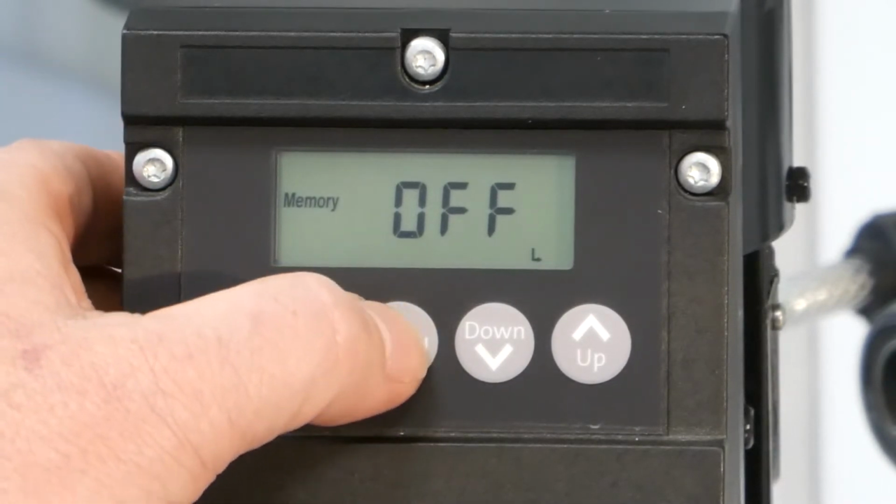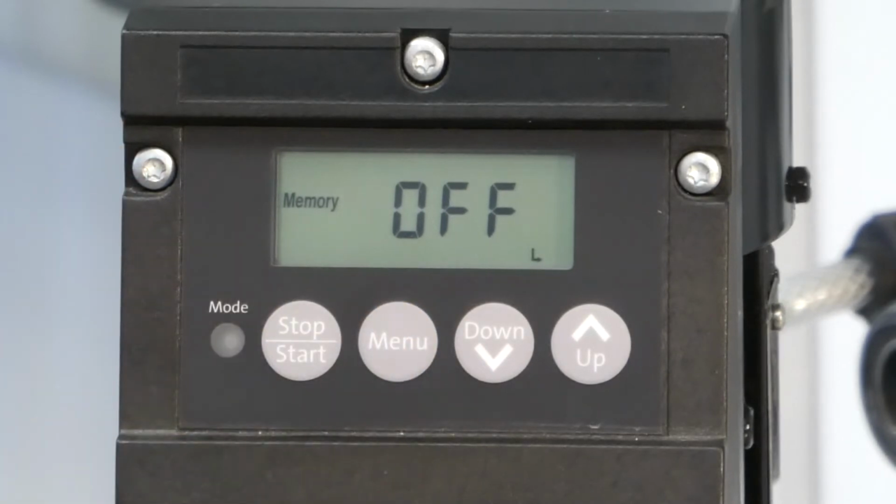You can switch on or off a memory, which helps you to store incoming pulse signals. In case there are more pulse signals incoming than the pump can work with, then the pump can store them if the memory here is on.